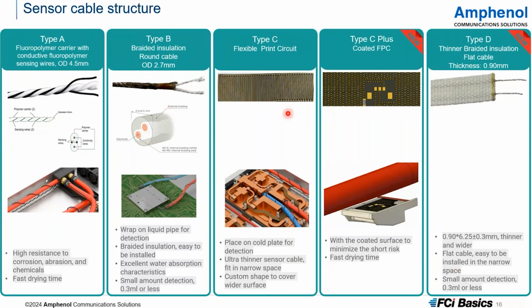The FPC type is also being used more and more due to the custom shape, and it's much thinner and wider. We call this FPC type Type C. And we also have an upgraded version, which we call Type C+. Type C+ has a coated surface to prevent the false alarms of Type C, which have caused a lot of trouble. So currently we are promoting the use of Type C+. Recently, we developed a new flat type, which is also a braided cable, but the thickness is just around 0.9 millimeter. We call it Type D. Compared to Type B, which is 2.7 millimeter, this new Type D can be placed in much thinner areas, especially on the cold plate.